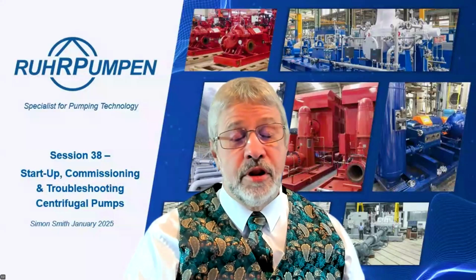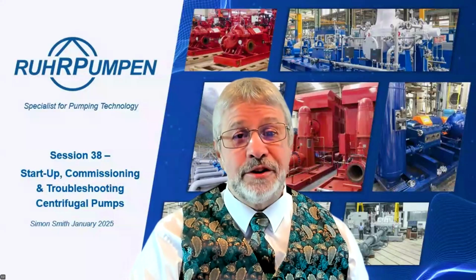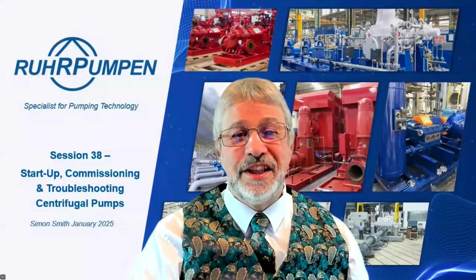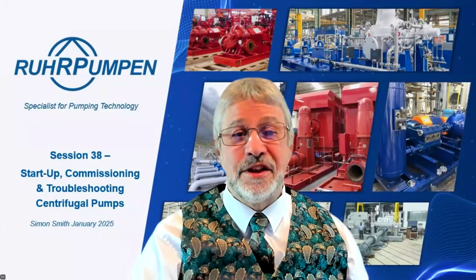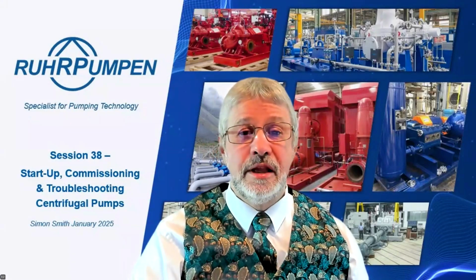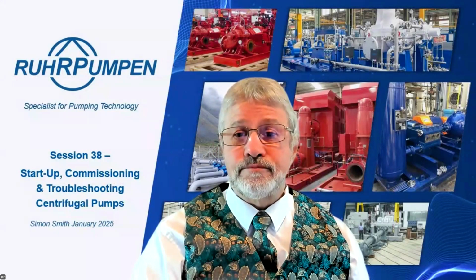Is it possible to replace a double seal plan with a single seal for a centrifugal pump? Yes, it can be done. Consult with the mechanical seal supplier. Don't install a seal without checking with a seals vendor that it's suitable for the process conditions that you want it to work with.